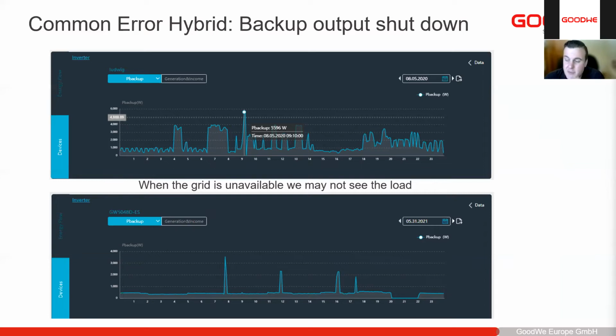And then in the second one, when the grid's unavailable, we are limited to our battery discharge current. So the inverter will not over discharge those batteries. So if you have a limited battery discharge, you see we can't run it for too long on that, then you can't see the load that caused it to shut down. So if you do have any shutdowns like this and you are wondering exactly what it is, you can just contact support and they will see a recovery error from these devices to see exactly the reason for it to shut down.